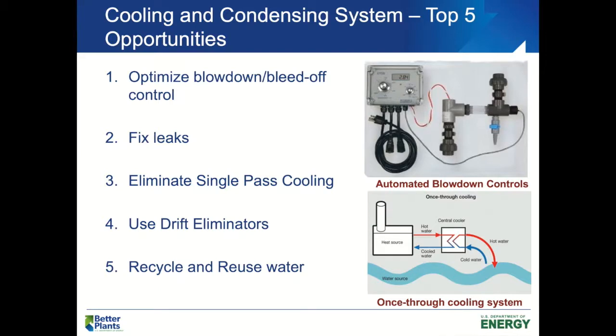So the water stream in our cooling and condensing system is pretty much the cooling tower blowdown, which again has a really high conductivity, right? So it's going to be really tricky trying to reuse that water. Maybe one application you will look at is landscaping. Some of the plants could take the water directly from blowdown. So reusing might be tricky, but recycling is definitely an opportunity. But the only thing to note there is the economics, right? Would it be worth chasing the blowdown water and having a water treatment for it to be reused?